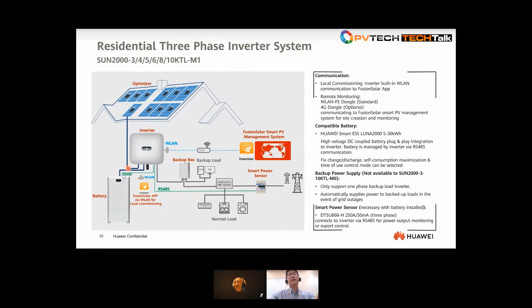For the design of the PV modules with the Huawei Smart PV Optimizer, we can get a very flexible design. We don't need to obey the conventional string design rules of putting all modules in one direction when connected in one string. Normally with 2 MPP trackers, you can only use 2 faces of the rooftop. But with Huawei's optimizer solution, you can put modules everywhere, connect them in series with one PV cable down to the inverter, and the string can be longer compared to a conventional string inverter.